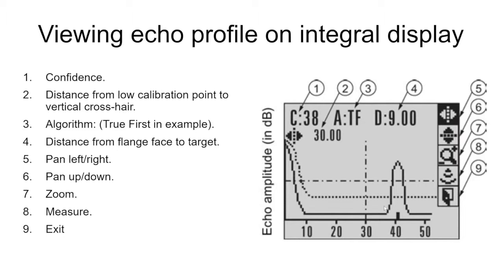To the right of that we have ATF. This is showing us that the algorithm is true first and that's going to be default, but depending on the application we may need to change that. To the right of that it shows D 9.00, telling us that the distance from the sensor flange or reference gauge is 9 feet away.